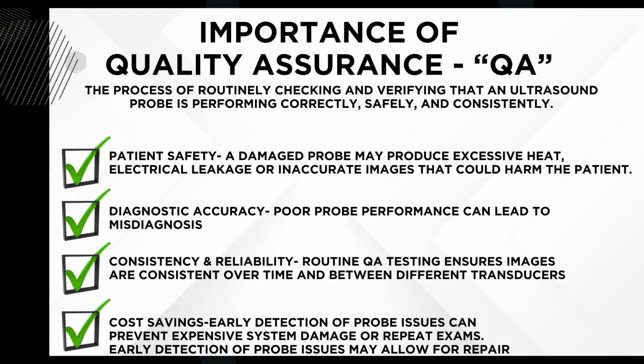The importance of quality assurance is, one, this process of routinely checking and verifying that an ultrasound probe is performing correctly, safely, and consistently. Obviously, the biggest thing is patient safety. A damaged probe may produce excessive heat, electrical leakage, or inaccurate images that could harm the patient. Diagnostic accuracy: poor probe performance can lead to misdiagnosis. Consistency and reliability: routine QA testing ensures images are consistent over time and between different transducers. And cost savings: early detection of probe issues can prevent expensive system damage or repeat exams, and may allow for repair rather than replacement of the transducers.